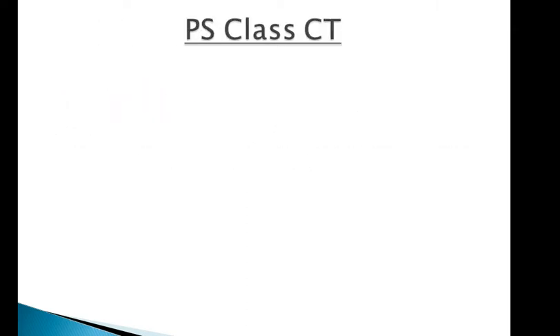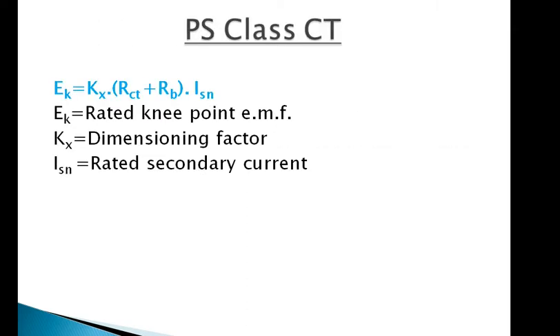Now we will check the protection CT sizing calculation for PS class CT. PS class CT is used in differential protection such as bus differential, generator transformer differential protection, and motor differential protection.